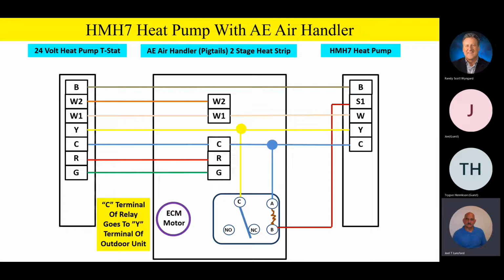The common terminal of the switching contacts on the relay is going to tie into that yellow wire going outside to the outdoor unit, from the thermostat to the outdoor unit. So anytime we have a Y call on the thermostat, it's going to have 24 volts power available to the common switching terminals on the relay.